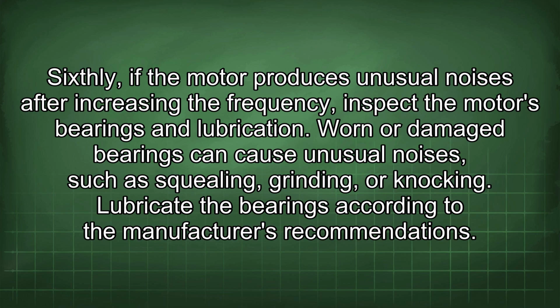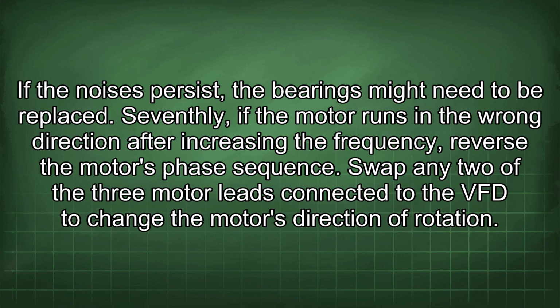Sixthly, if the motor produces unusual noises after increasing the frequency, inspect the motor's bearings and lubrication. Worn or damaged bearings can cause unusual noises, such as squealing, grinding, or knocking. Lubricate the bearings according to the manufacturer's recommendations. If the noises persist, the bearings might need to be replaced. Seventhly, if the motor runs in the wrong direction after increasing the frequency, reverse the motor's phase sequence. Swap any two of the 3 motor leads connected to the VFD to change the motor's direction of rotation.